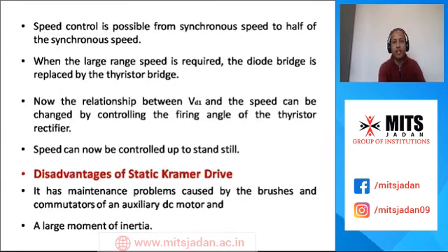There are certain disadvantages of this method. Basically, when we are using the static Kramer drive with a DC motor, there is a problem of brushes and commutators due to that auxiliary DC motor. There is a maintenance problem basically. And secondly, it requires a large moment of inertia for this particular system. In order to remove these disadvantages, we can modify this Kramer drive.